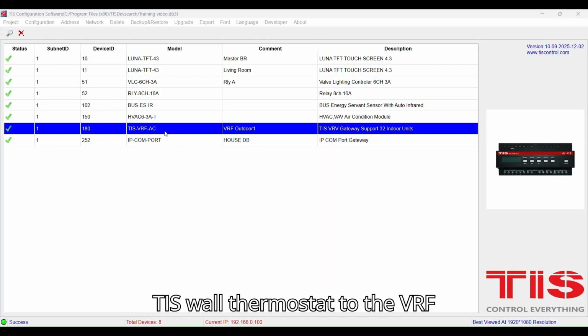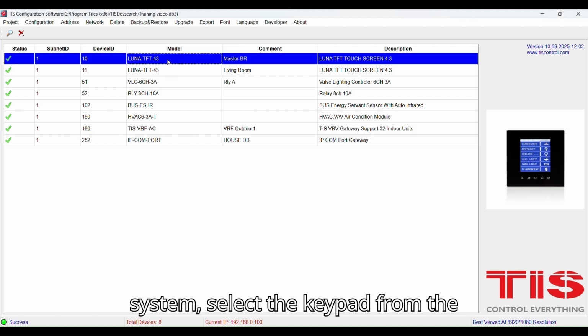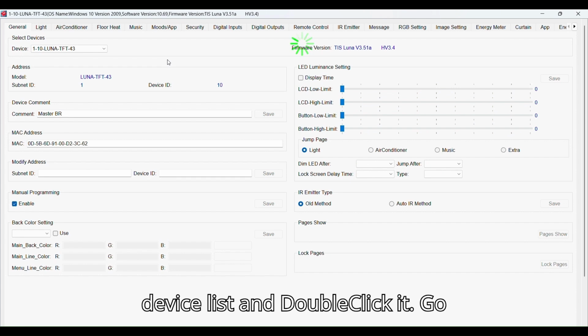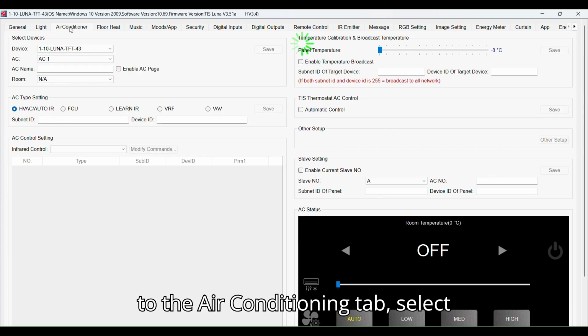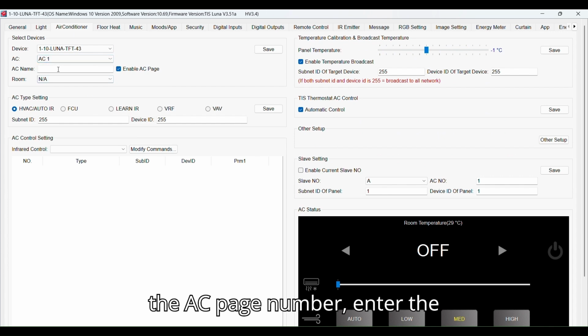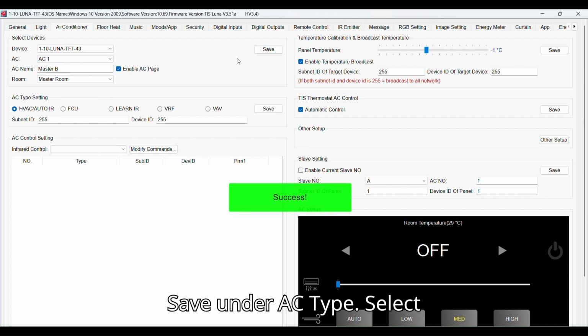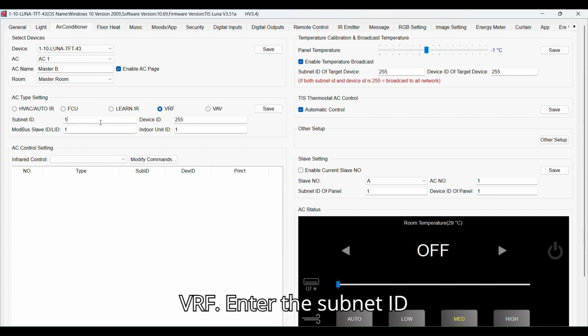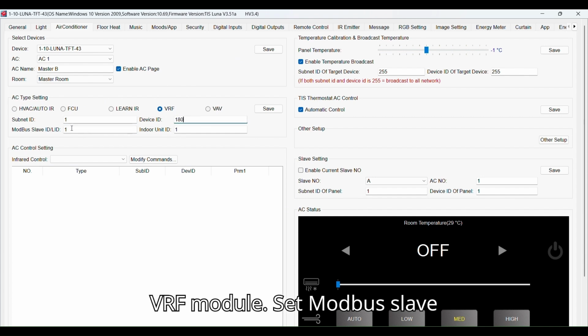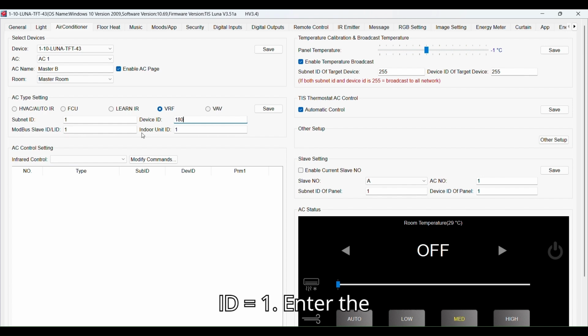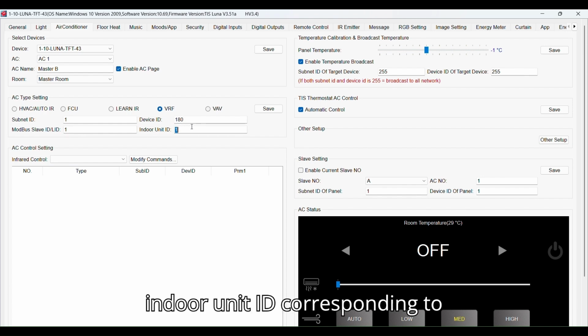To assign a TIS wall thermostat to the VRF system, select the keypad from the device list and double-click it. Go to the Air Conditioning tab. Select the AC page number, enter the name, choose the room, and press Save. Under AC Type, select VRF. Enter the subnet ID and device ID of your VRF module. Set Modbus slave ID equals 1. Enter the indoor unit ID corresponding to that room.